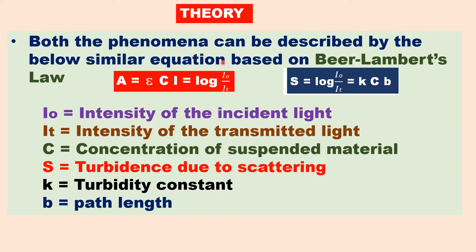Let us discuss the theory of these methods. Both phenomena are based on Beer-Lambert's law, and a similar equation is used. According to Beer-Lambert's law, A = ε·C·l = log(I₀/It). In turbidimetry, S = log(I₀/It) = k·c·b, where I₀ is the intensity of the incident light, It is the intensity of the transmitted light, c is the concentration of the suspension, S is the turbidance due to scattering by the suspended particle, k is the turbidity constant, and b is the path length.